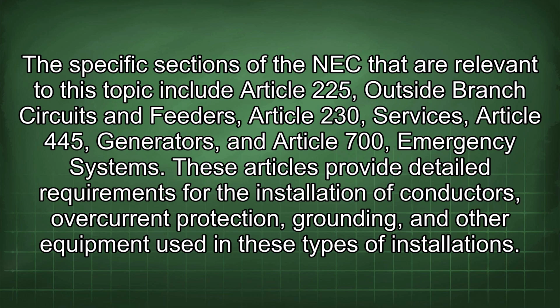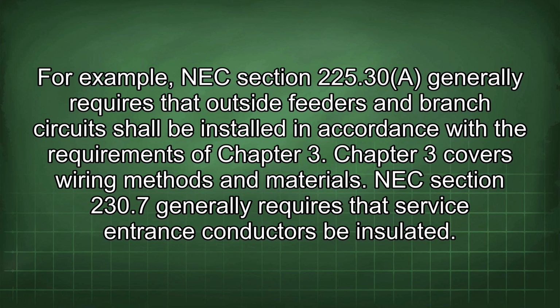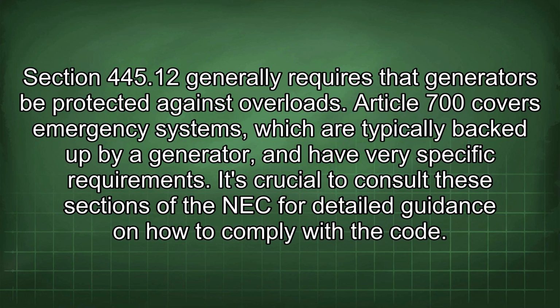These articles provide detailed requirements for the installation of conductors, overcurrent protection, grounding, and other equipment used in these types of installations. For example, NEC Section 225.30 generally requires that outside feeders and branch circuits shall be installed in accordance with the requirements of Chapter 3. Chapter 3 covers wiring methods and materials. NEC Section 230.7 generally requires that service entrance conductors be insulated. Section 445.12 generally requires that generators be protected against overloads. Article 700 covers emergency systems, which are typically backed up by a generator and have very specific requirements. It's crucial to consult these sections of the NEC for detailed guidance on how to comply with the code.